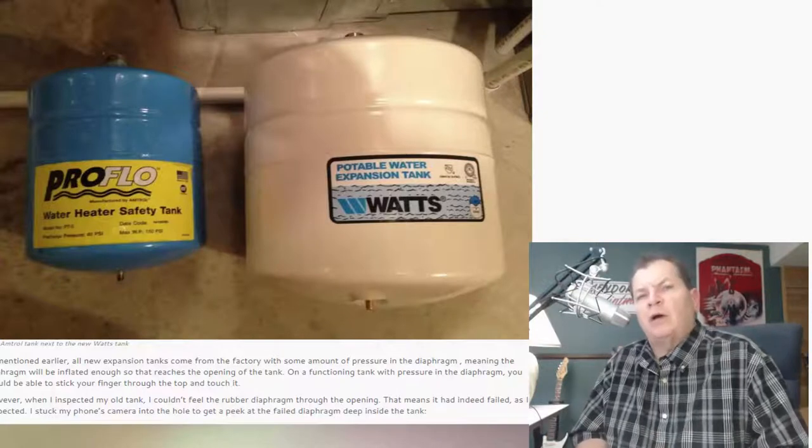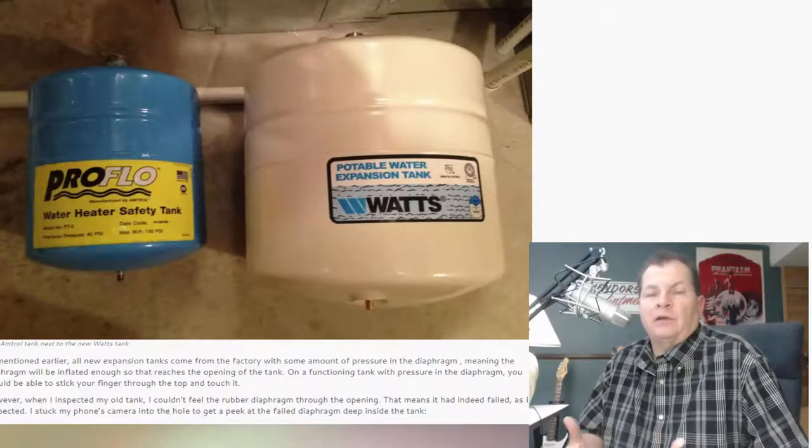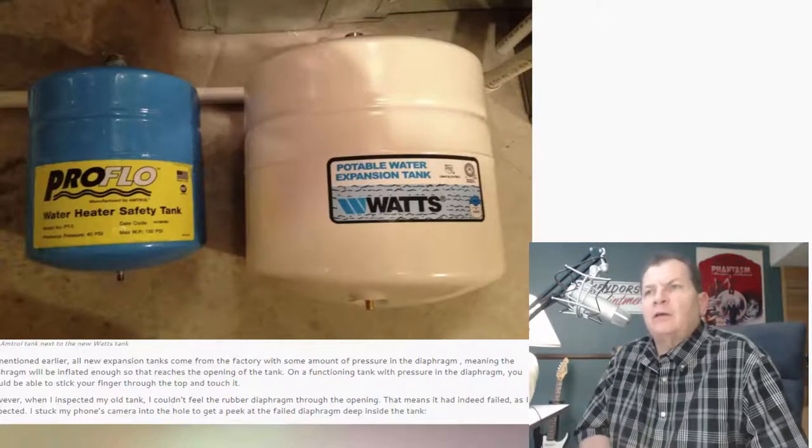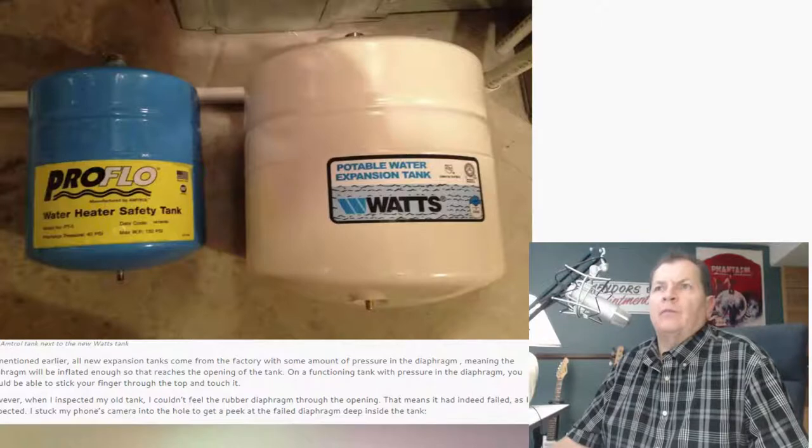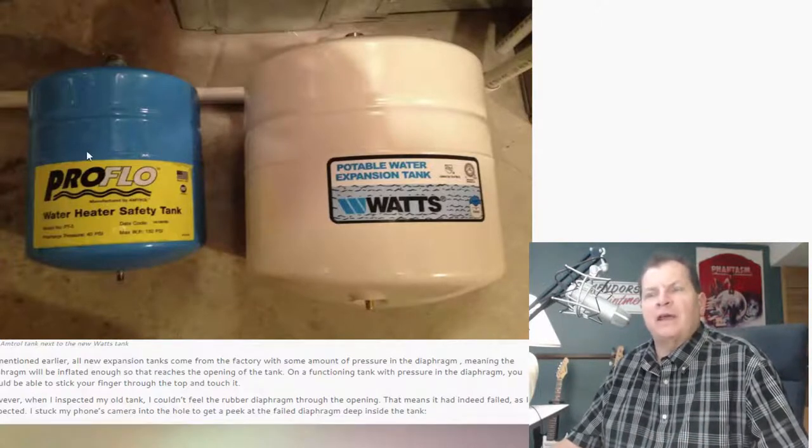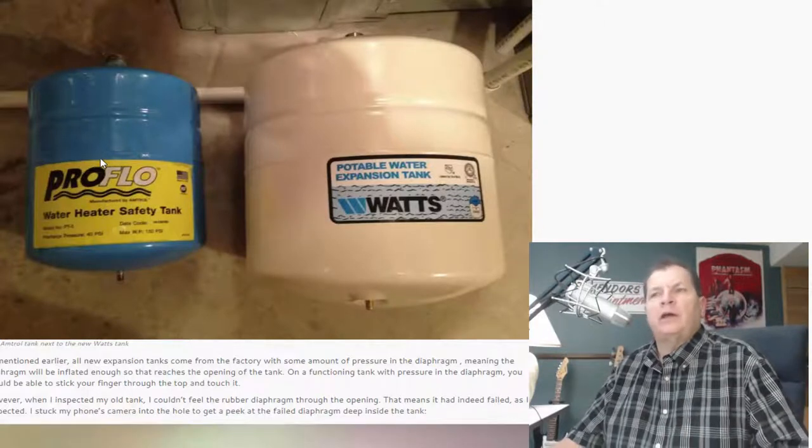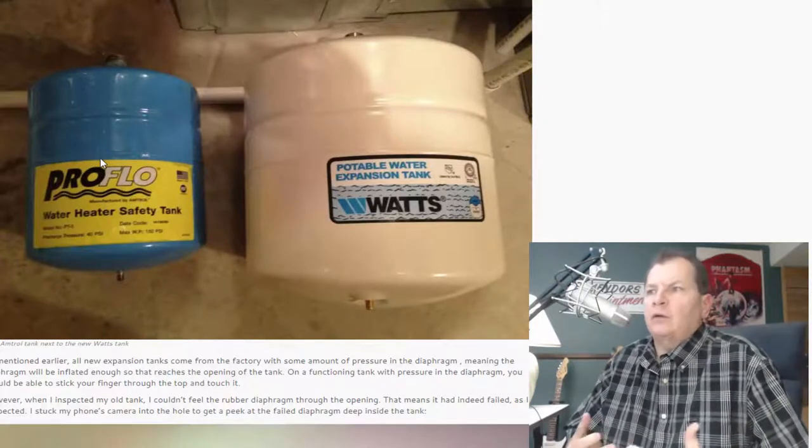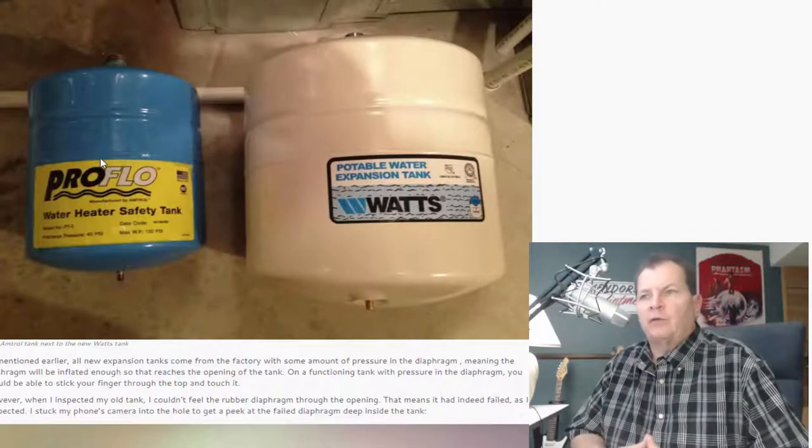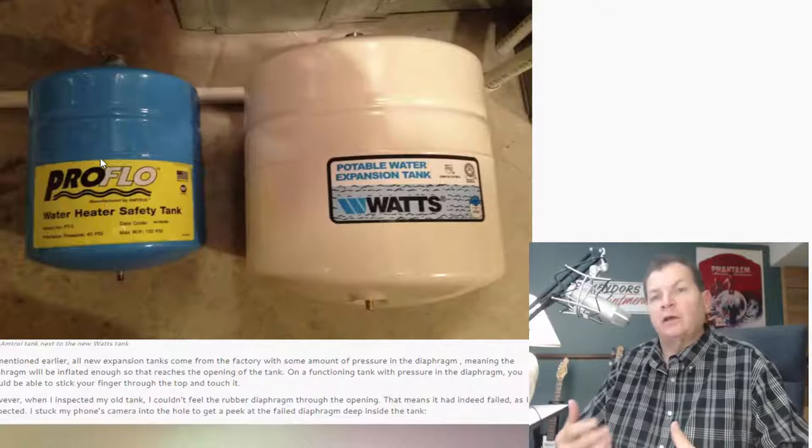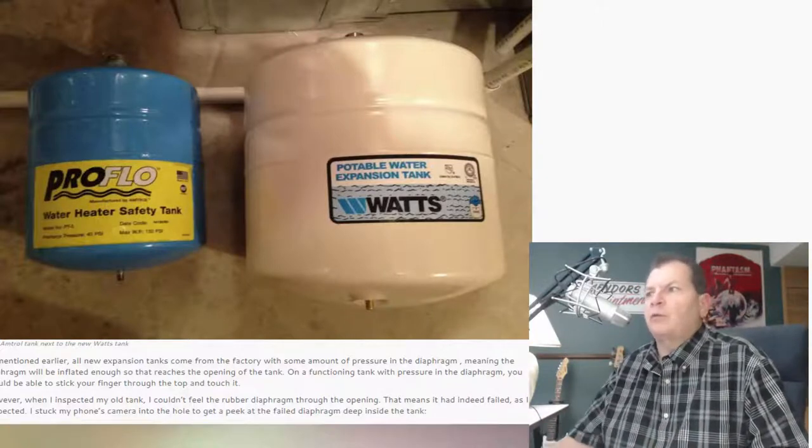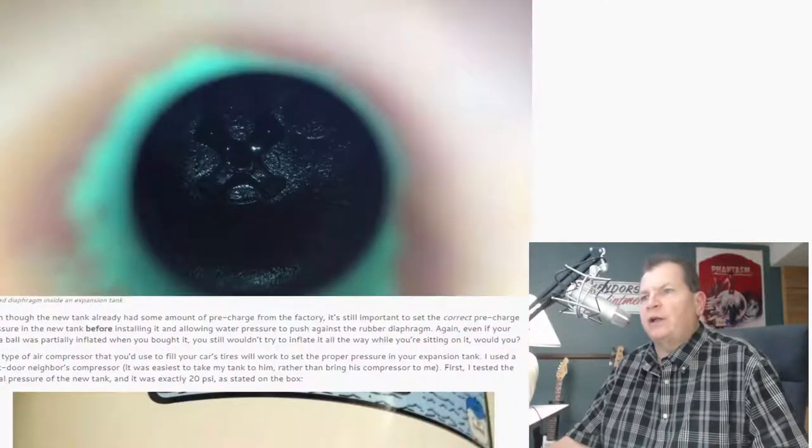It's got to be sized a certain way also. You could have a tank that's, if you've got a 75 gallon water heater and, depending on your street pressure, this tank could be too small. And let's say the plumber didn't do you a favor and maybe installed something that was right off his truck instead of actually upsizing you to the correct expansion tank. This could be some of the little problems you're having. And maybe that's why you look for this video.